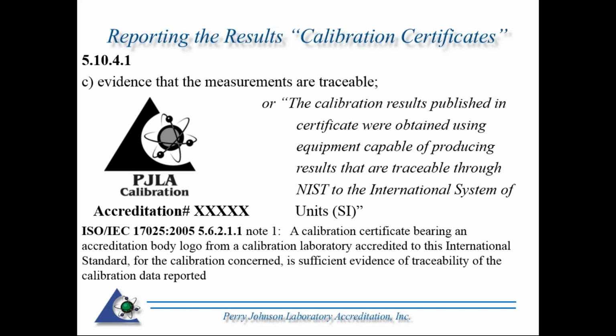We may see somebody referencing traceability to NIST. That is incorrect. It needs to be through NIST to the international system of units. So like I said, if you did not use a logo, but had that particular statement on there, that would be sufficient evidence of traceability.